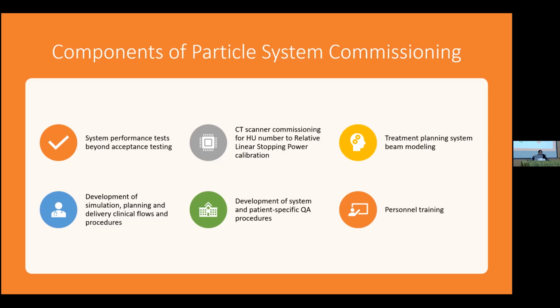Knowing what your quality control and QA procedures could be, daily, weekly, monthly, so you can do proper tests during acceptance and commissioning so that your regular quality assurance is as meaningful as possible. Then a lot of this data needs to go into whatever treatment planning system you're getting, and that's a different vendor, so you need to know how that's going to work together. And then, of course, the training of the people. This is during the acceptance test and your clinical commissioning, and to some extent during the technical commissioning, that's when you're also getting your training.